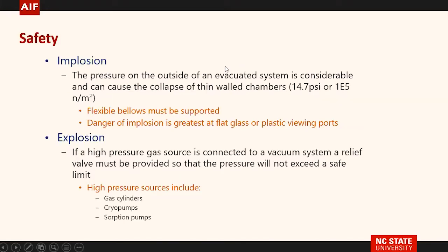Safety is very important. I tell my students that I can be hurt, but you can't. If I don't give you the information for you to do your job safely, that is not acceptable. You have to realize that when you have a system pumped out, you have a tremendous amount of pressure on it. 14.7 pounds per square inch, or 10 to the fifth newtons per meter squared. So if something's flexible, you have to support it like a bellows. And if you've got a piece of glass, you have a danger of implosion if you've got a viewing port.